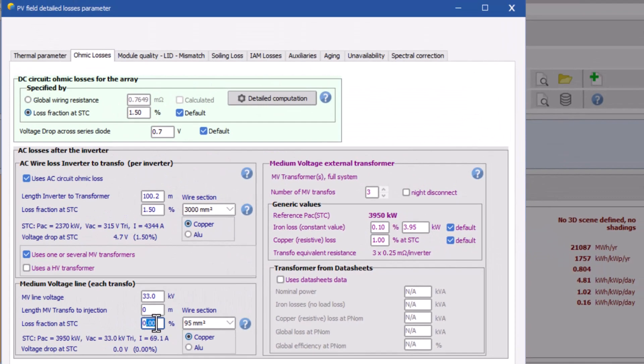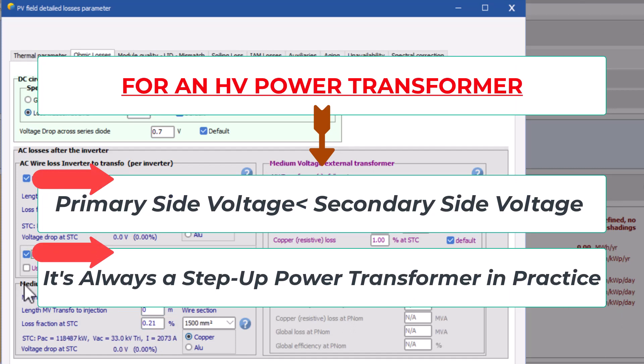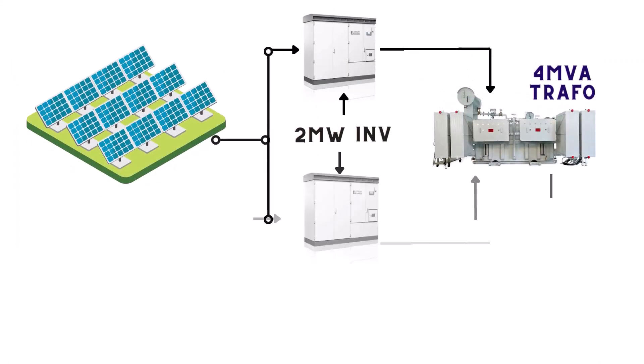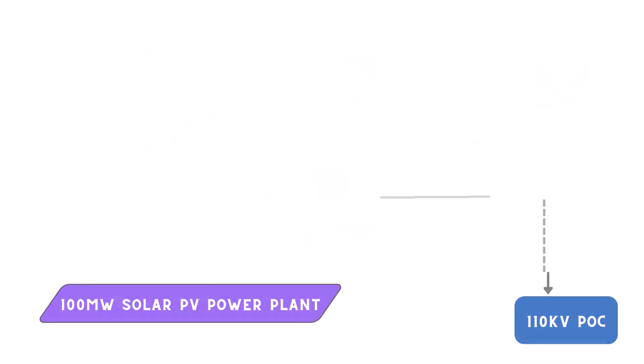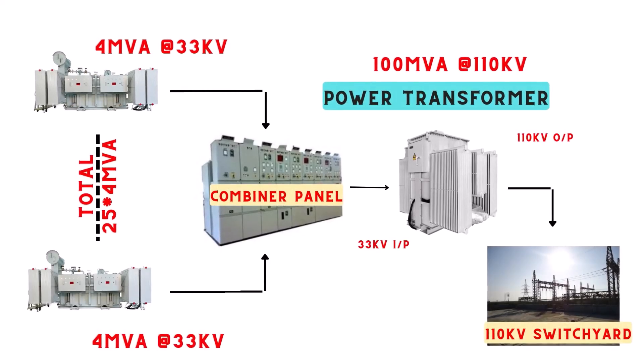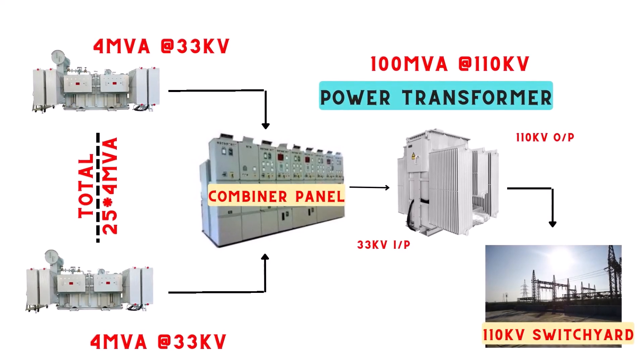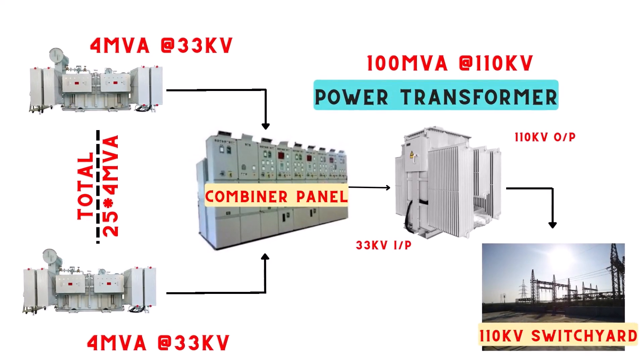Now coming to the HV transformer, this type of transformer is required when you are connecting your PV system to the grid where the voltage level is more than the secondary side voltage of your available solar transformer. For an example, we are designing a plant of 100 megawatts. We are using solar inverter MV transformers with output voltage of 33 kilovolts, and the grid voltage of nearest point of connection is 110 kilovolts.